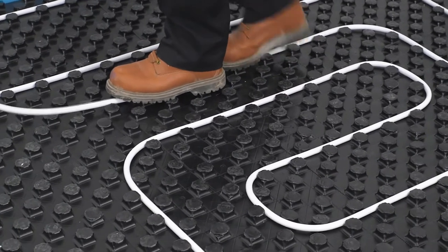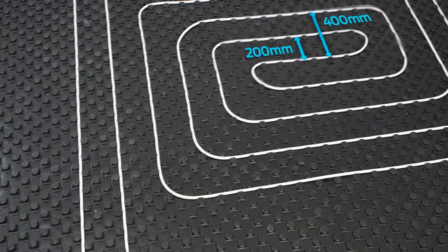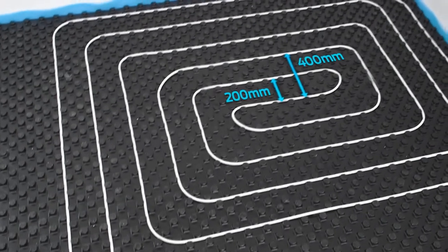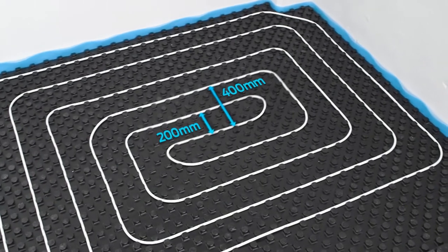Because the pipework spirals in and then returns in the opposite direction, the initial inward pipe spiral has to be double the designed distance apart. So a 200mm design centre would mean initially laying the inward spiral at 400mm.